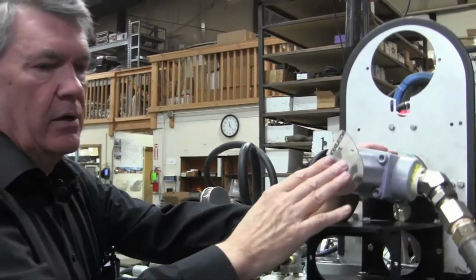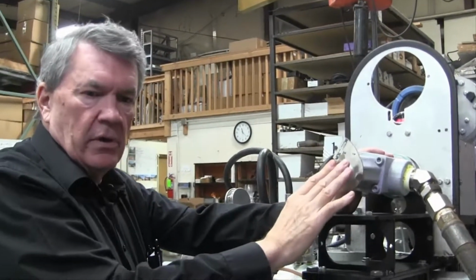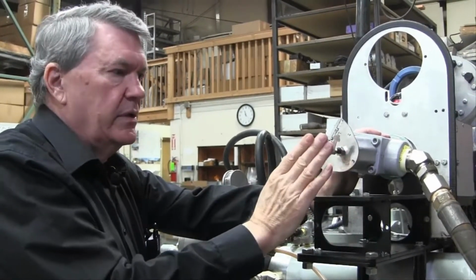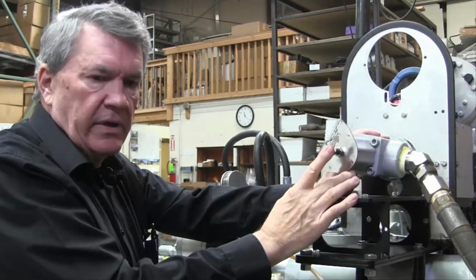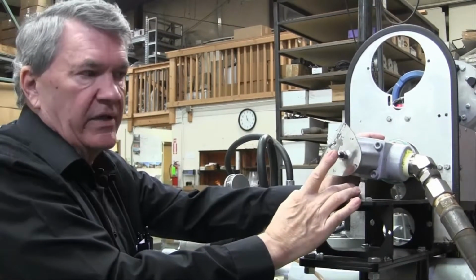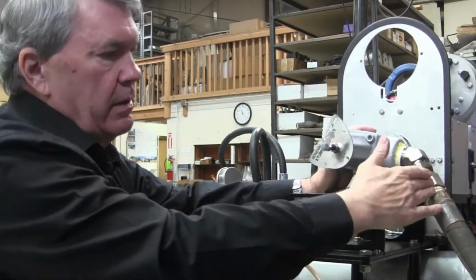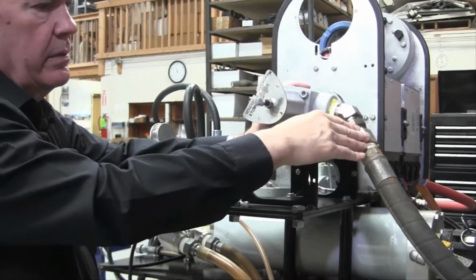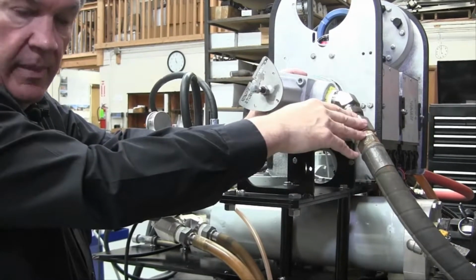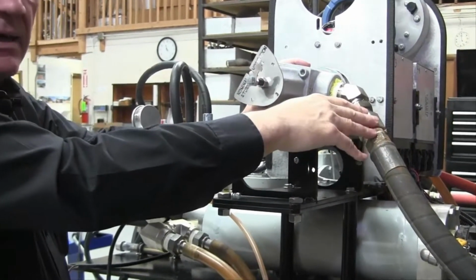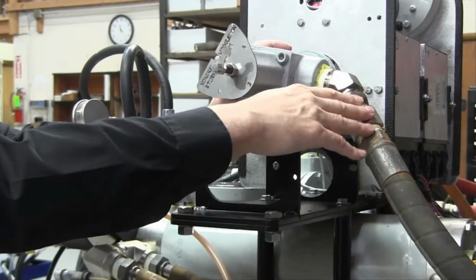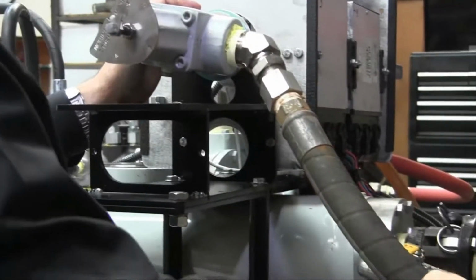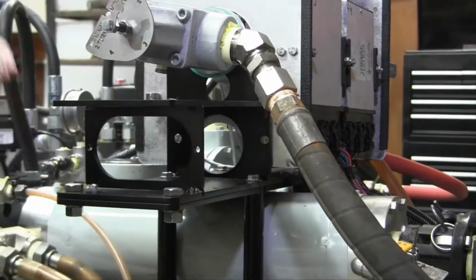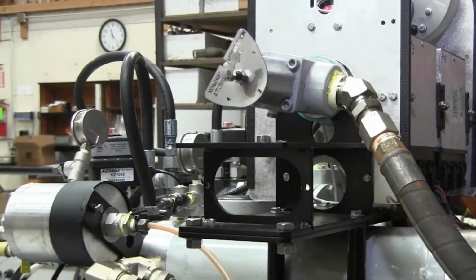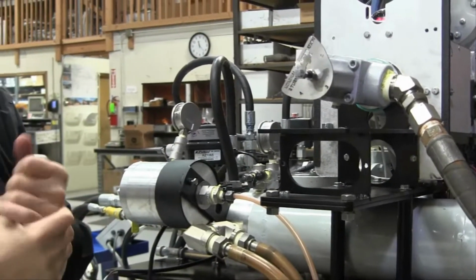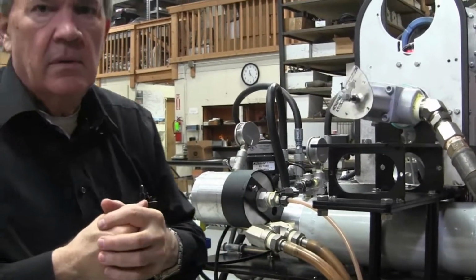So it allows for better regulation, something that we have learned in the last 3 years, that the discharge valve actually needs to be located right here at the outlet of the mass meter. And of course from here the flow is going to maybe a single manifold. It can go up to 9 manifolds if required. So there's a lot of splitting that needs to be done and controlling that needs to be done with harnessing, etc. But in almost all cases it's all economics.